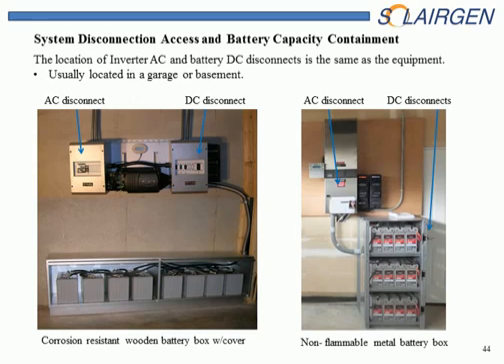Here's a couple of examples of battery systems. Typically the battery systems are installed in one of two types of boxes. Either a wooden box that has an anti-corrosive paint or coating inside of it, or preferably a metal box, which of course is fireproof and anti-corrosive. But I've seen a lot of battery systems that simply set on the concrete floor, on a pad, but they're set open without any cover on them because they're sealed batteries. If they're sealed batteries, they don't lose any gases to the atmosphere, and technically, as long as the room has a little bit of ventilation in it, they could be open.